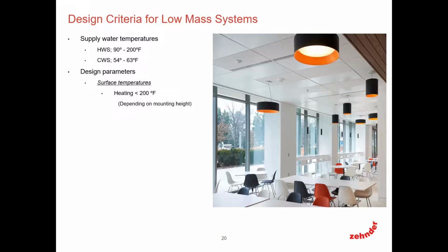All right, so let's talk a little bit about design criteria, what the approach is when we're looking at these systems, and a little bit more detail on how we would design them. So generally, hot water systems, somewhere between 90 to 200 degree water on the entering side, chilled water side, somewhere between 54 and 63. What will drive your entering chilled water will be your dew point, and we'll talk a little bit more about that when we talk about controls and piping. So 54 to 63 on the chilled water side.